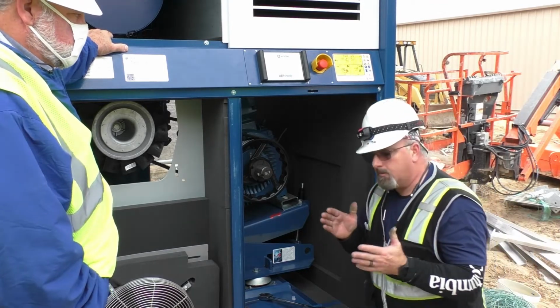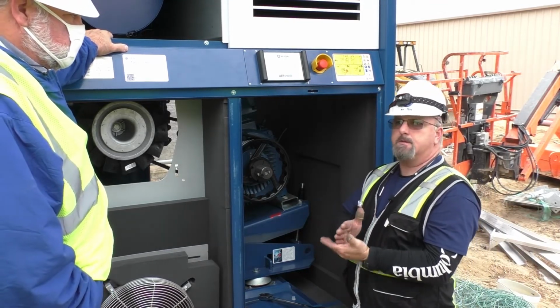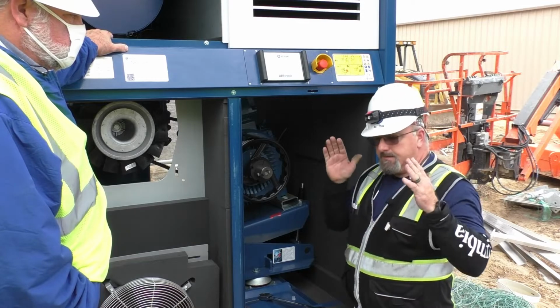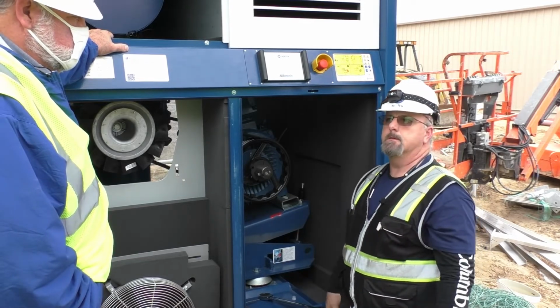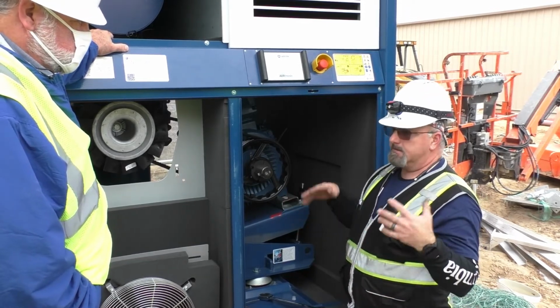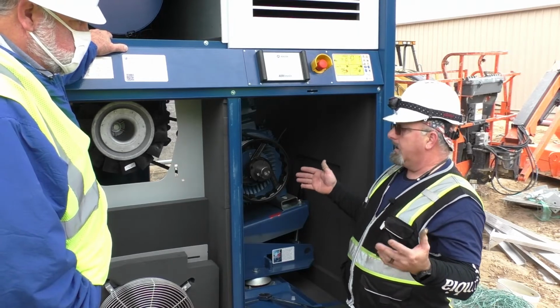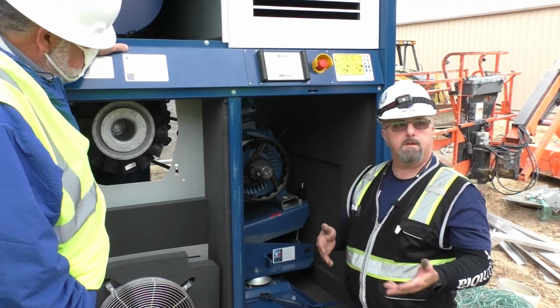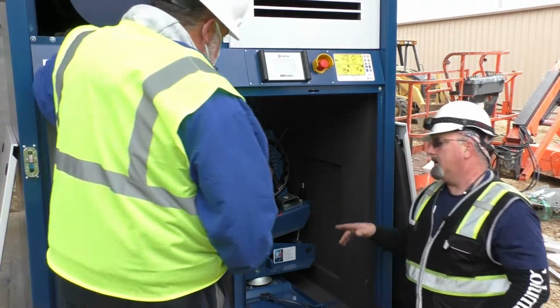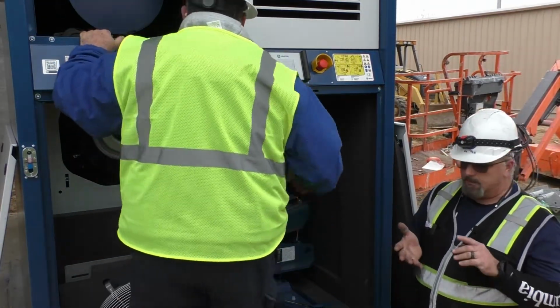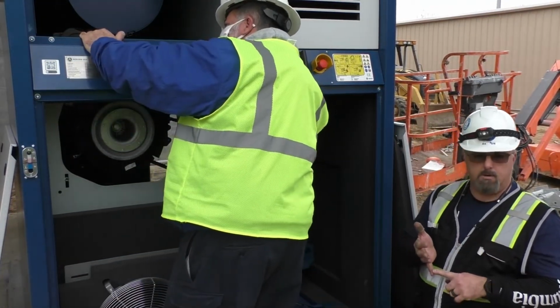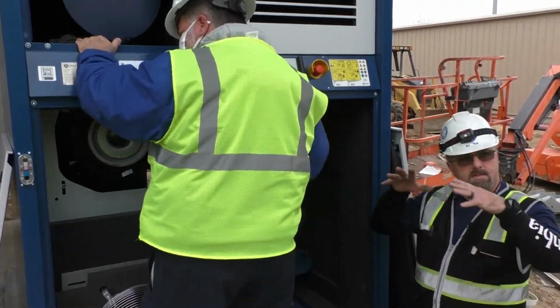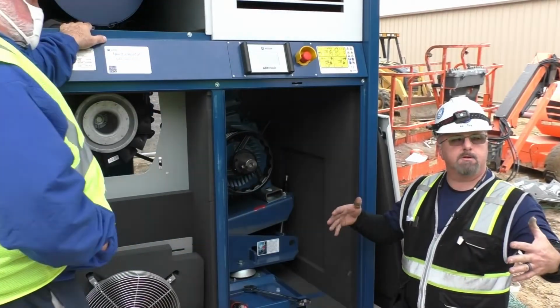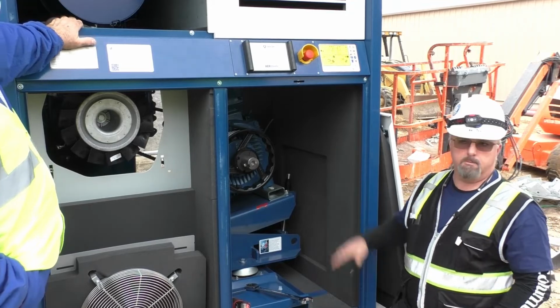So that way, no matter what, from the beginning of that belt service to the end of that belt service, it has the same tension on that belt drive. There's no question and there's no doubt about you're maintaining the appropriate tension on that unit. And when they do the belt calculation, it's not only for the speed of the blower, it also helps to set that tension to make sure that you minimize slippage on the belt drive.